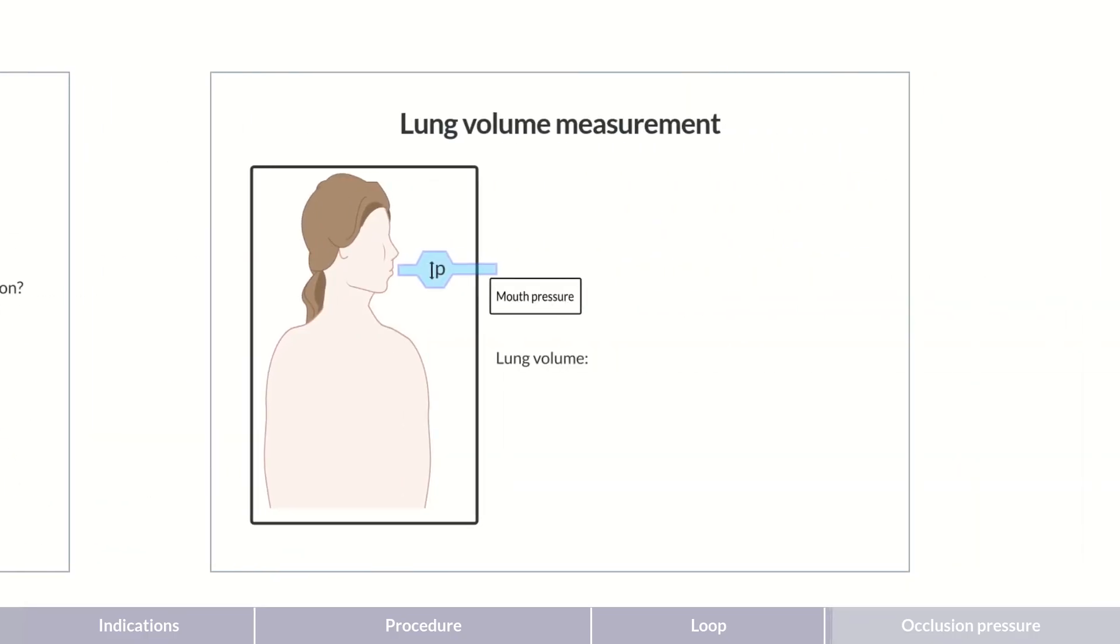To calculate the lung volume, we need to know the displaced volume, as well as the relative change in volume in the lung. The latter can be determined using the pressure sensor in the mouthpiece. After the patient has breathed normally for a while, occlusion pressure is measured.